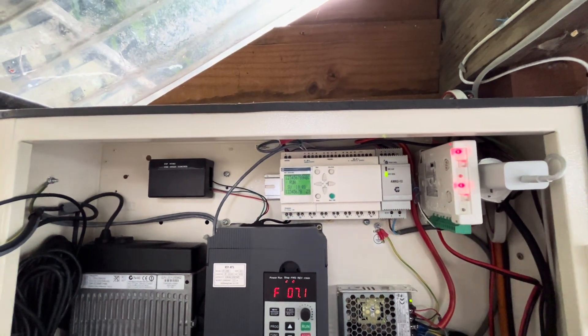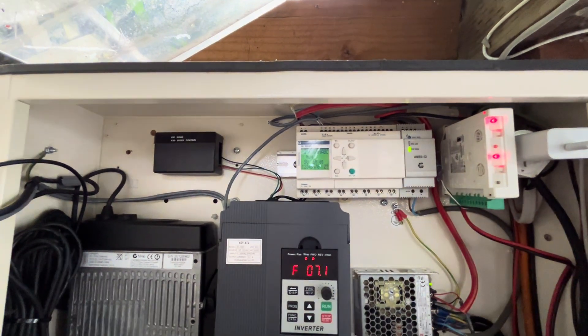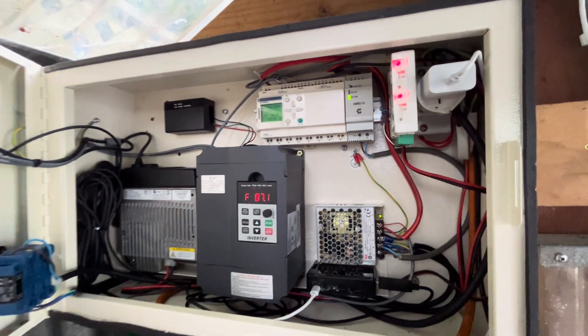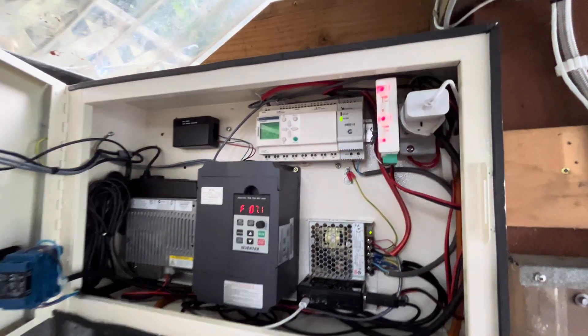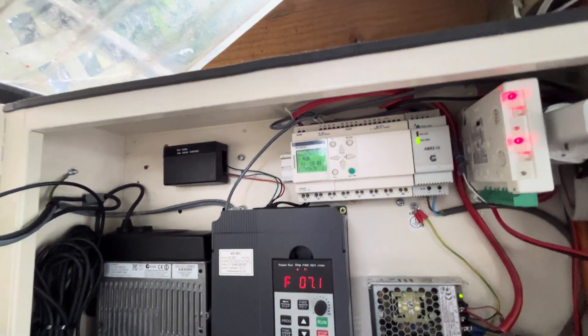This now does all of the timing for the VSD, and after 8pm, even if there's an input to the PLC, it will not run up the VSD. There is still a potential failure point — the PLC or the VSD itself could glitch out — but that's very unlikely, and if it did happen there is a manual isolator on the side here.